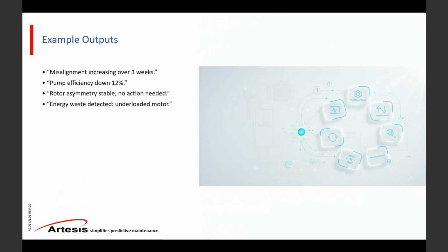And of course, all of this information is also available in dashboards and charts and numbers, but the LLM outcome would be to just read this and understand that I need to do some optimization, because the load profile of this motor is giving us this output, which is that there are potential savings opportunities if we properly size this asset. So now you can automate that first pass expert style interpretation consistently, quickly, and across the whole fleet.